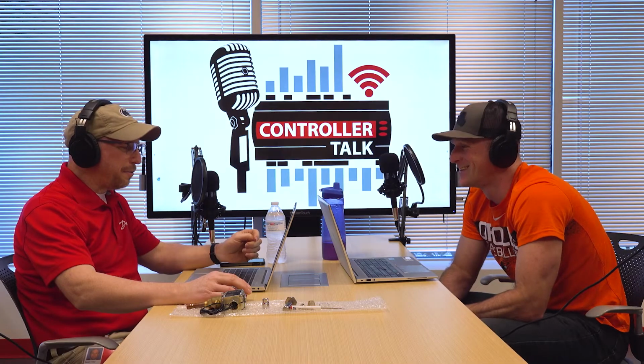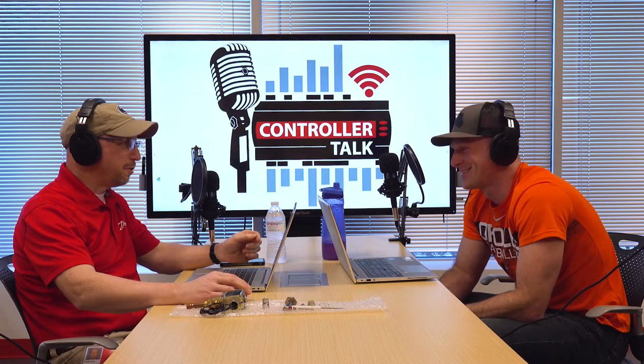Yes. Well, Chris, you'll remember from last time that the AKV valve was released in 1987. And this is a very common electronic expansion valve. And you'll also remember that you correctly guessed that more than 3 million of these have been installed so far. Guess being the key word there. A guess nonetheless, but it was a good guess. So AKV stands for Adap-Kool valve. In the Danfoss realm, Adap-Kool refers to technology that uses intelligent algorithms for controlling, including building a history of valve cycling that can be used if it detects a sensor failure.